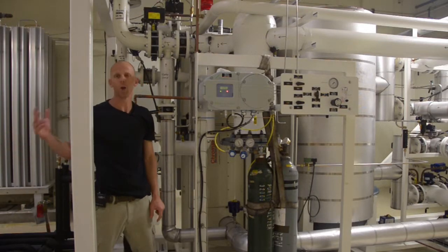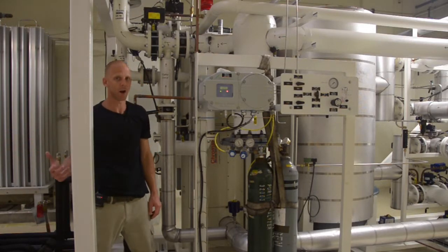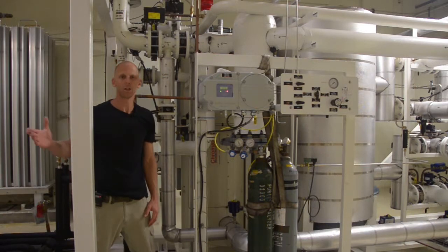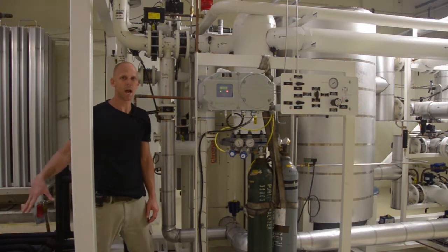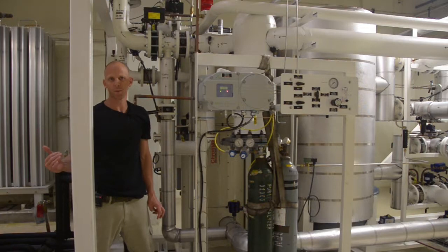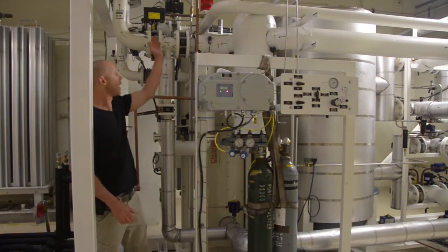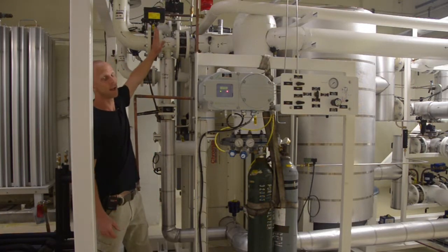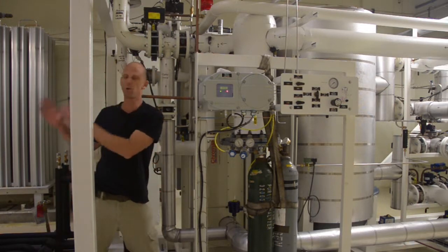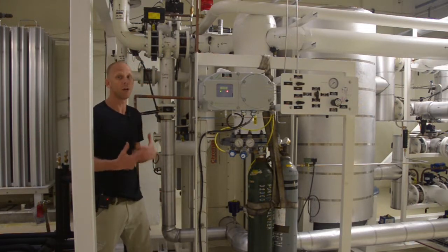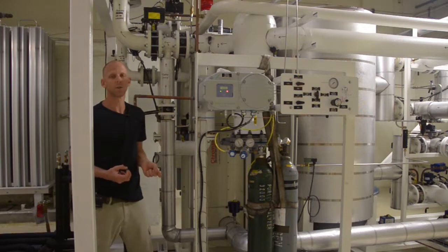In other words, if the oil lubrication system for our turbine is running. If for some reason the lube oil pump shuts down or the lube oil pressure drops below a certain set point, this valve will close. And why it does that: we do not want process air moving through our cold box with the potential to spin our turbine unless we have lubrication.